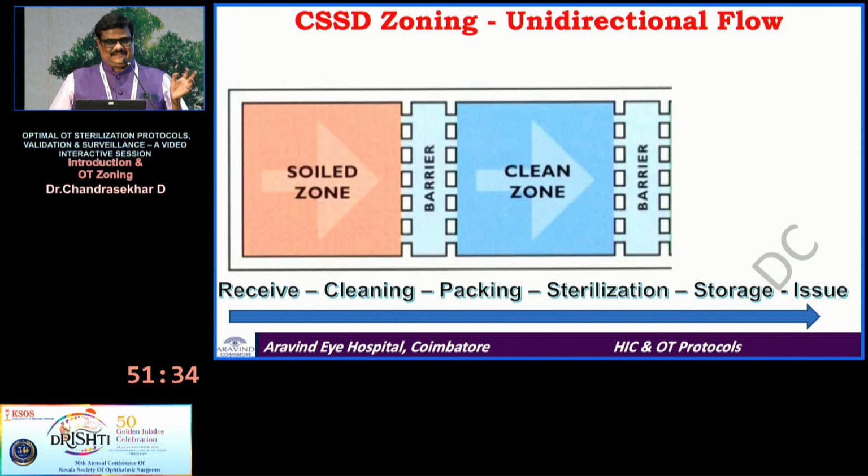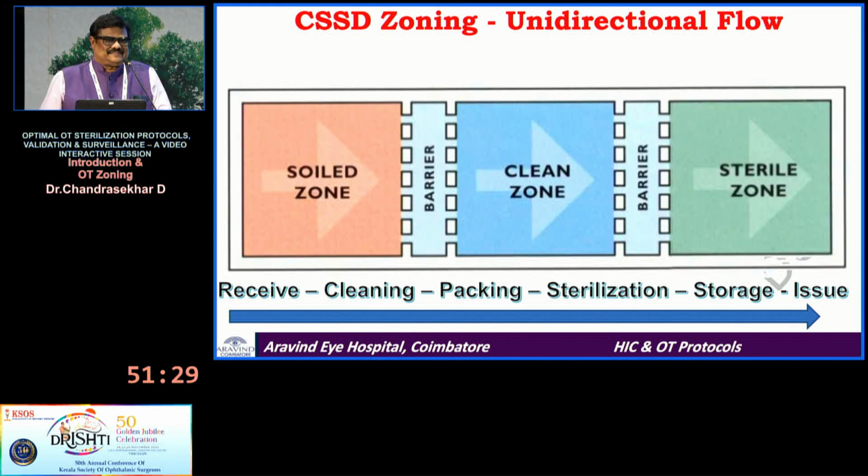Rajiv will show. Once it is cleaned and packed, then it goes into the sterile zone where your autoclave will be. So between the clean zone and the sterile zone, it is ideal to have an autoclave, which is a double door autoclave.